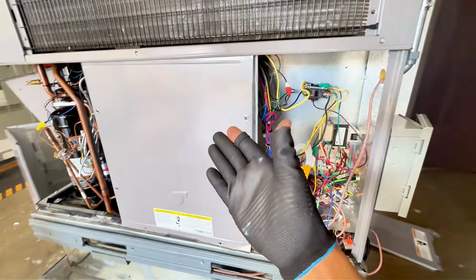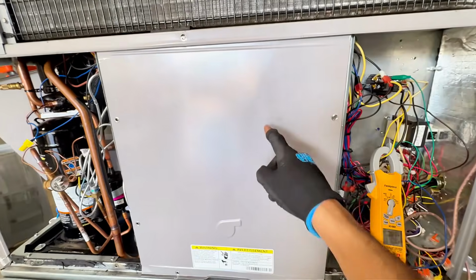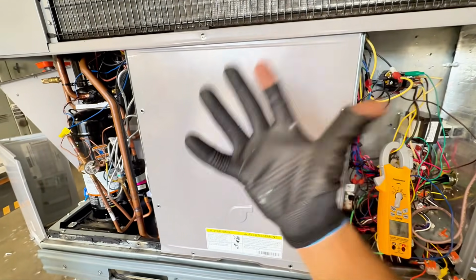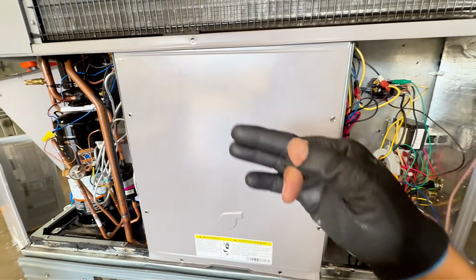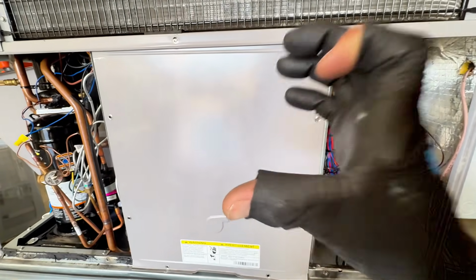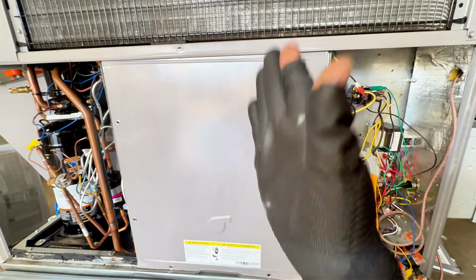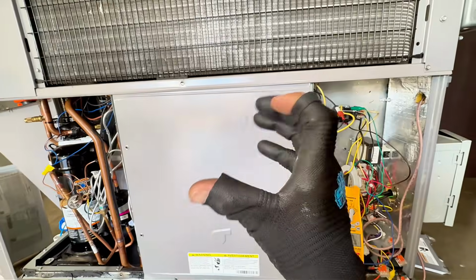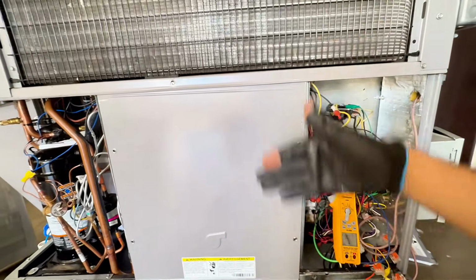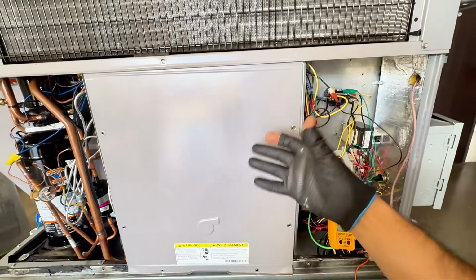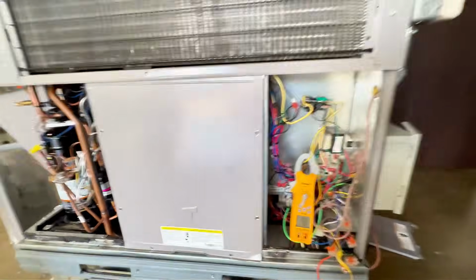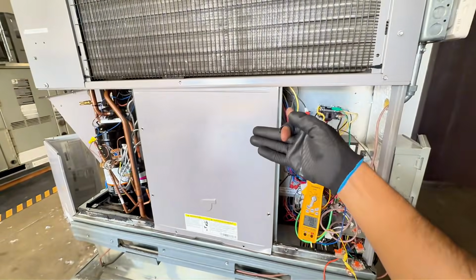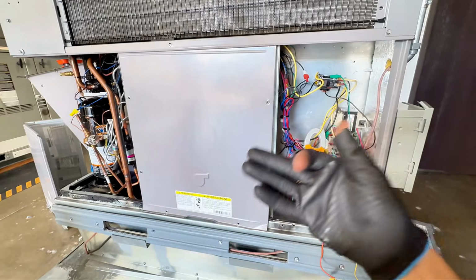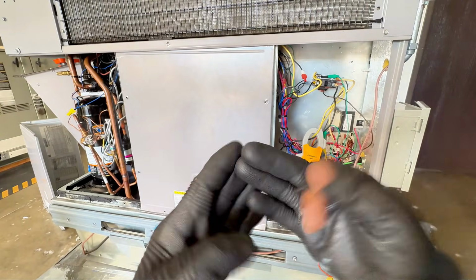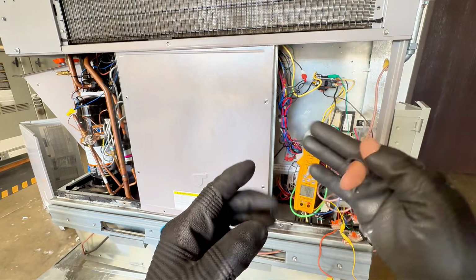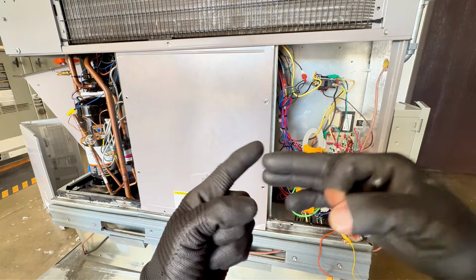So with an ECM motor, because right now we have 24 volts going on number 5, the highest speed, it's trying to maintain a constant torque for that speed. So regardless, if there's a restriction, it's going to ramp up more to make up for that restriction. But guess what? If you're pulling more current now, that's how these modules go bad. Now, don't get me wrong, they also go bad because of power surges. But this is why it's so important to change out the filters.